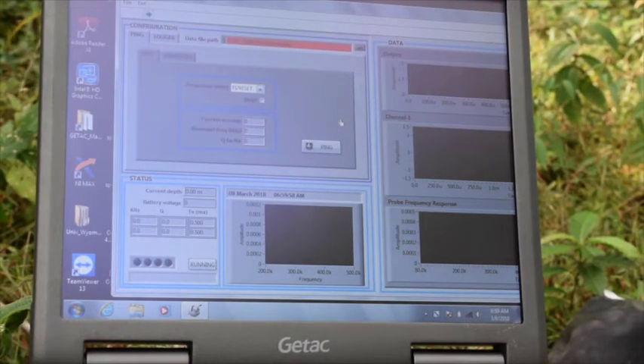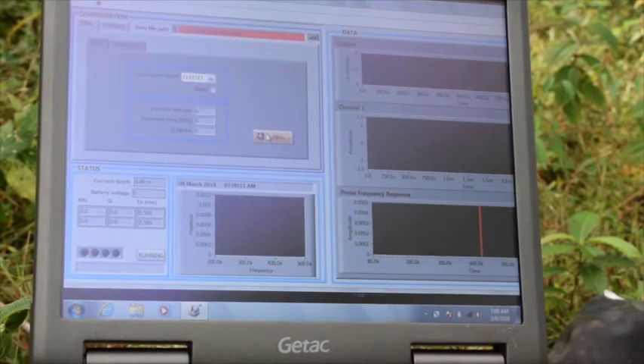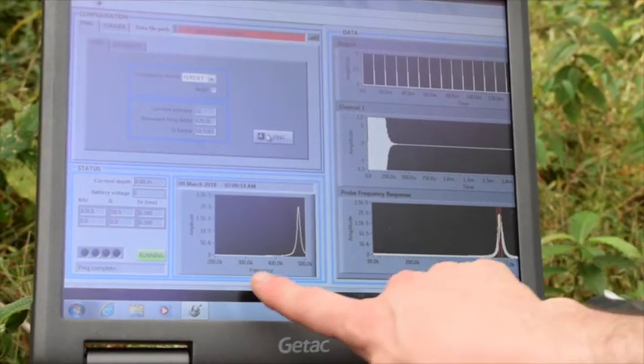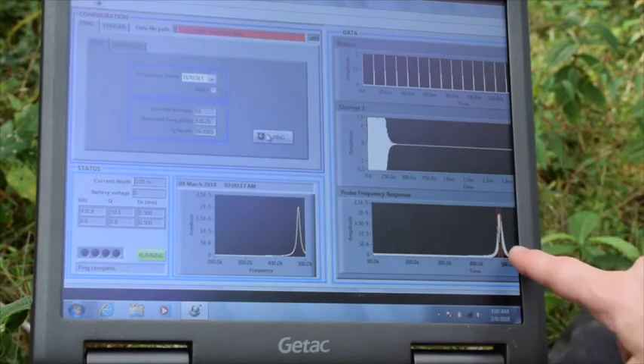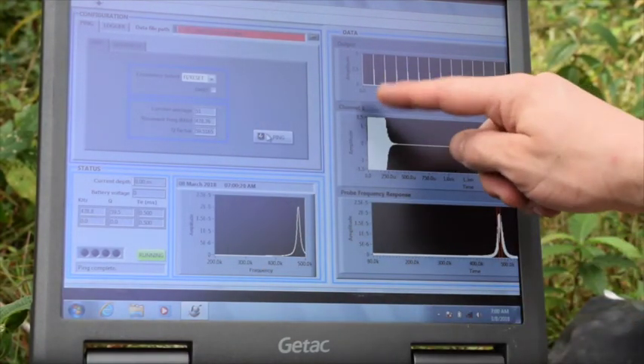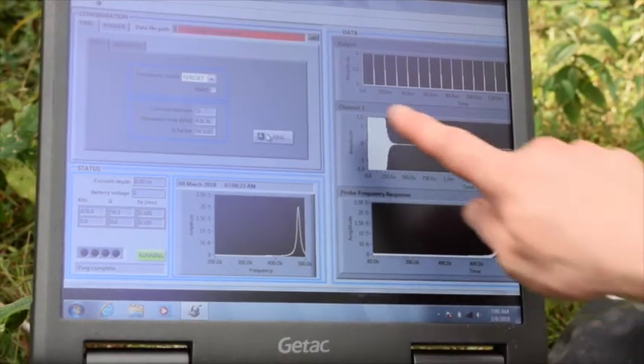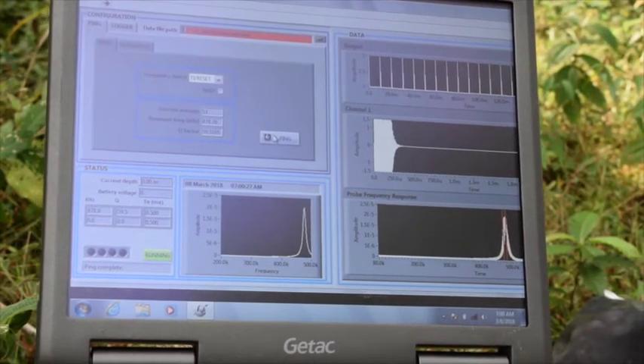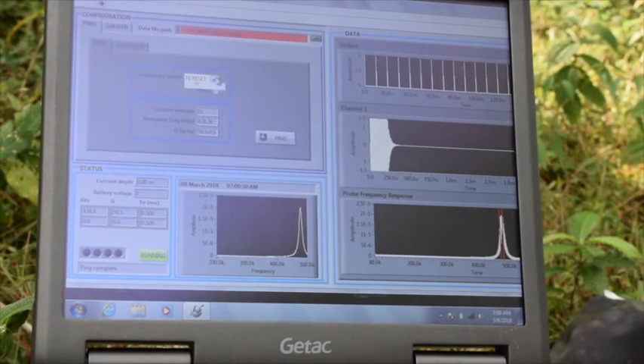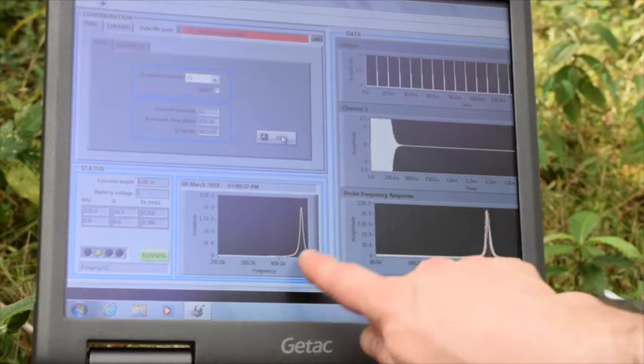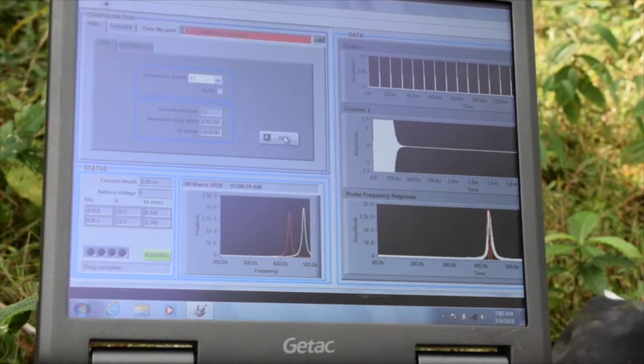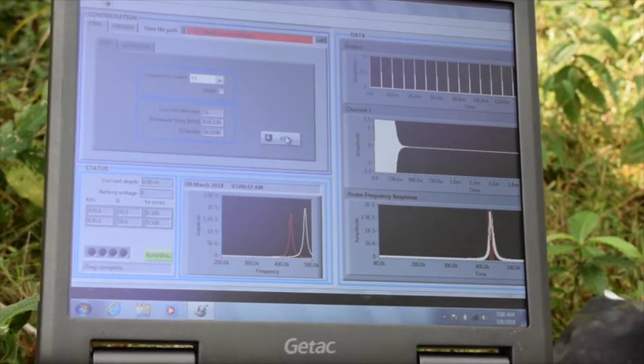So now that we have the probe plugged in, the instrument on, and the computer ready, it's not in the well yet. The probe is not in the well. So the first thing we can do is just check to make sure it's all hooked up correctly, and you can just press the ping button that shows in the middle of the screen. And what you're looking for is a nice clean peak in both of these bottom windows, and then a lot of high amplitude signal followed by no signal in the time window on channel 1. If it looks anything different than this, then that's a problem. And you can ping also the frequency too, and it'll show up as a slightly different peak. But basically the same idea. You want these to be clean peaks and then a clean time series. So once you're done with that, then we can move on to putting the probe in the well.